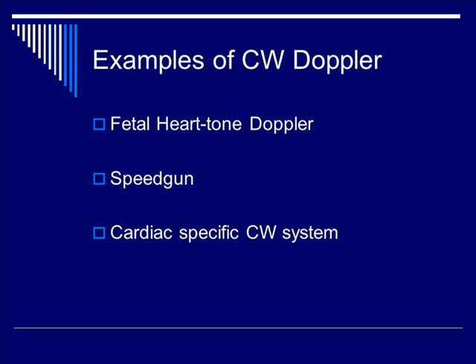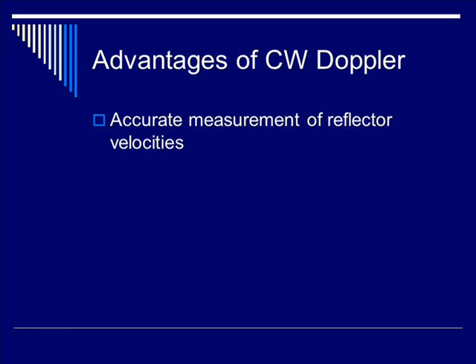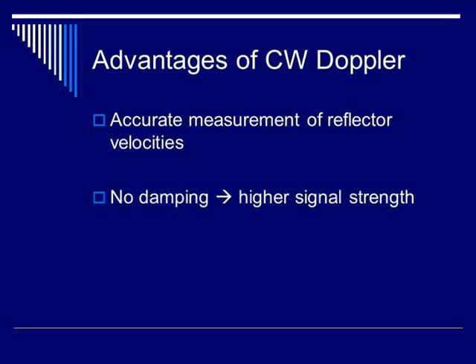Some examples of continuous wave Doppler include fetal heart-tone Doppler, speed guns, and cardiac-specific continuous wave systems. Advantages of continuous Doppler include accurate measurement of reflector velocities. There is no damping, therefore you have higher signal strength, and there is no aliasing.